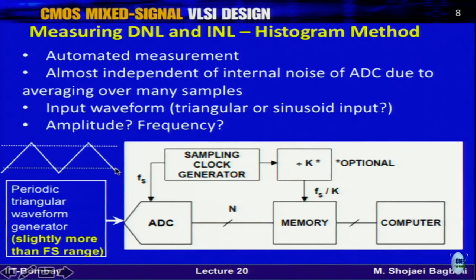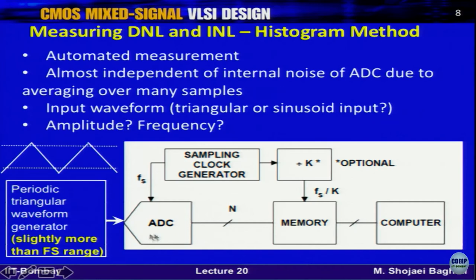With a triangular waveform slightly above full scale, you have overflow hits at the extreme codes. Excluding the first and last codes (2^n - 2 valid codes), the ideal number of hits per code is M_T / (2^n - 2). If the ADC has non-linearity, some codes will have more hits (wider segments) and some will have fewer hits (narrower segments) — these are called wide codes and narrow codes.